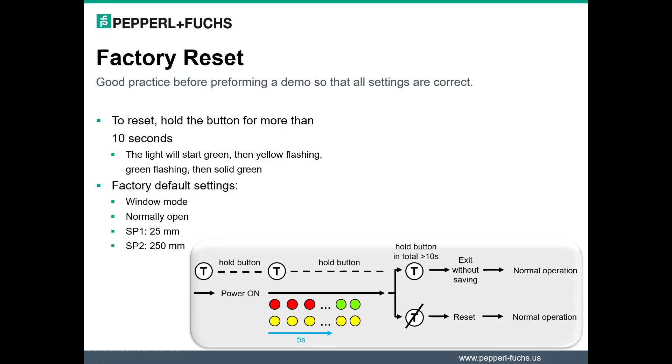Now we will begin discussing what you need to do to program your sensor with push button. First, before you do any programming, it is good practice to factory reset the sensor. This ensures that the settings that you place on the sensor are the ones that you want. To factory reset the sensor, hold the button for more than 10 seconds. The light will start green, flash yellow, flash green, and then become solid green again.